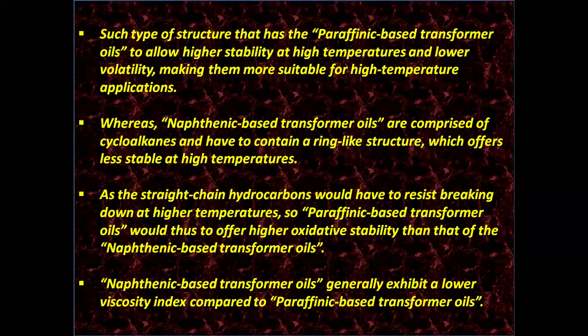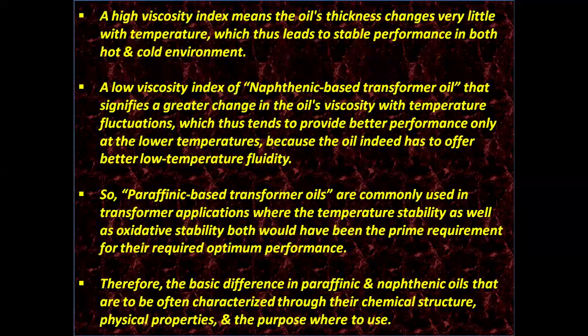Naphthenic based transformer oils generally exhibit a lower viscosity index compared to paraffinic based transformer oils. A high viscosity index means the oil's thickness changes very little with temperature, which leads to stable performance in both hot and cold environments.